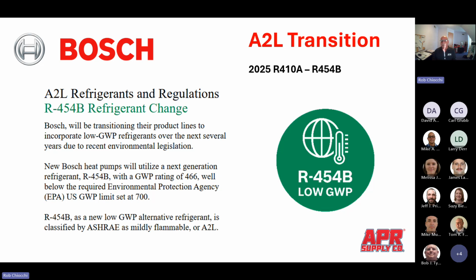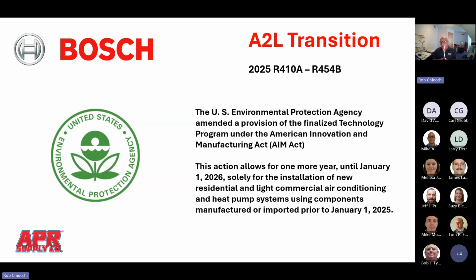Bosch IDS has made the commitment to R454B as their refrigerant of choice moving forward. So as we move through the timeline of 2025, we will be transitioning the Bosch IDS equipment from R410A to R454B. So what does that timeline look like? As part of the AIM Act, as of January 1, 2025, no manufacturer is allowed to produce a piece of equipment that uses a refrigerant of a global warming potential above 700. In other words, no more R410A equipment as of January 1, just merely 2 weeks ago.